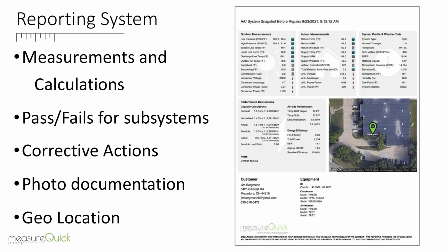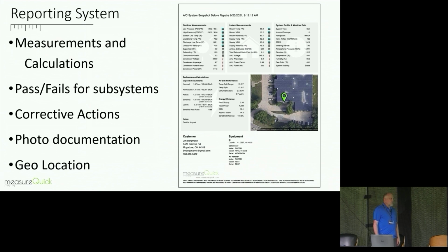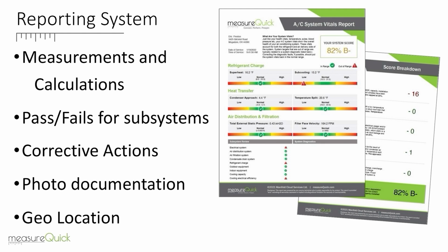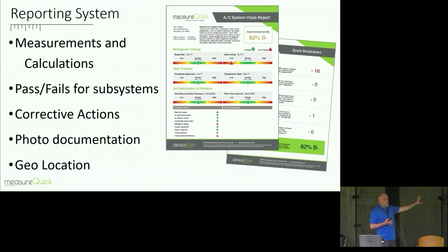Reporting. Obviously, a lot of you have seen our standard report, which does our measurements and calculations, the pass, fails, corrective actions. But here in about 15 days or so, we're going to release this new report, which is a consumer forward-facing report that actually grades the system. So it does your measurements and calculations, your pass, fails, photo documentation, geolocation, but it also takes and runs an analysis on that system and actually grades based upon your heat transfer, your refrigerant charge, and your air distribution and filtration. And so your new installations, you should get somewhere between 95 and 100%, and it's pretty spot on there.